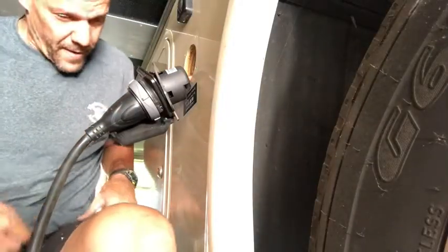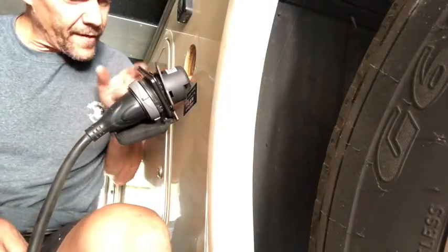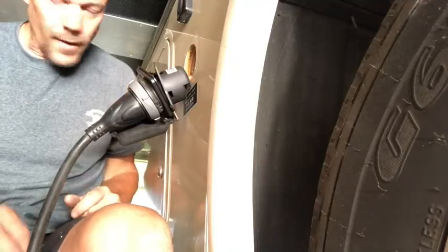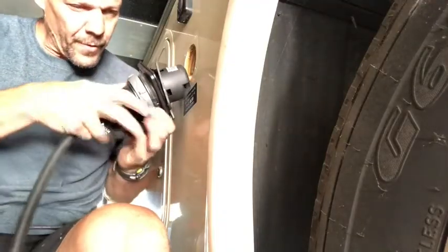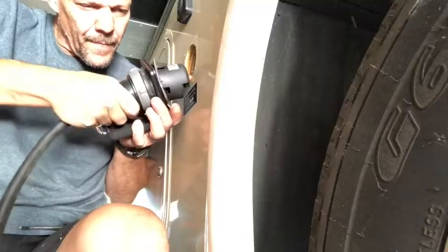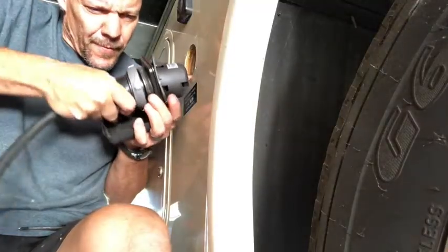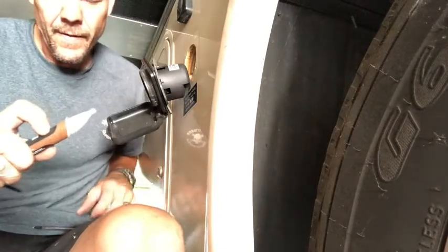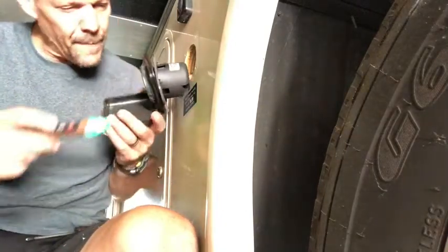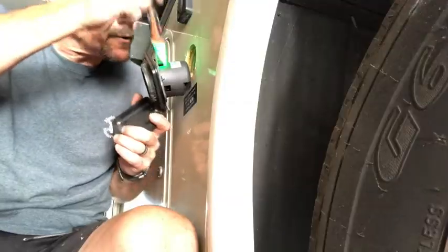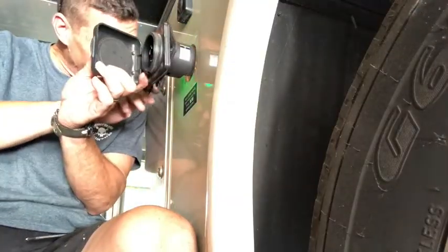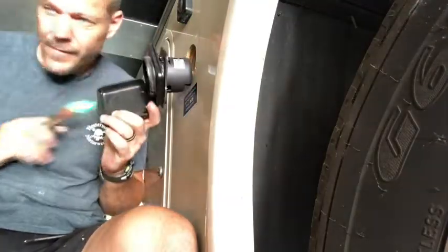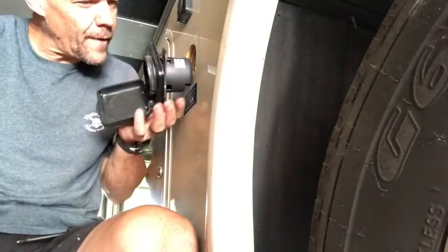The next step is to take this cover off and look at the terminals in there. So I'm going to unhook this cable, then check again with my sensor to make sure I don't have power before I start sticking a screwdriver in here anywhere. Okay, this is clear, no power.